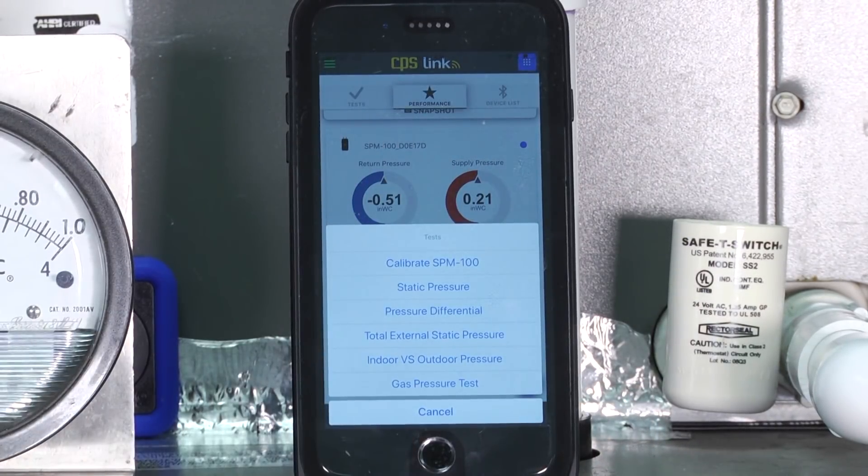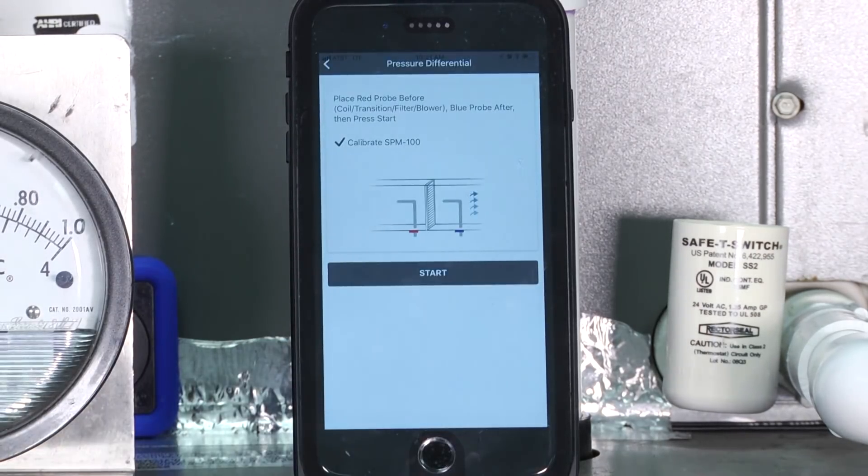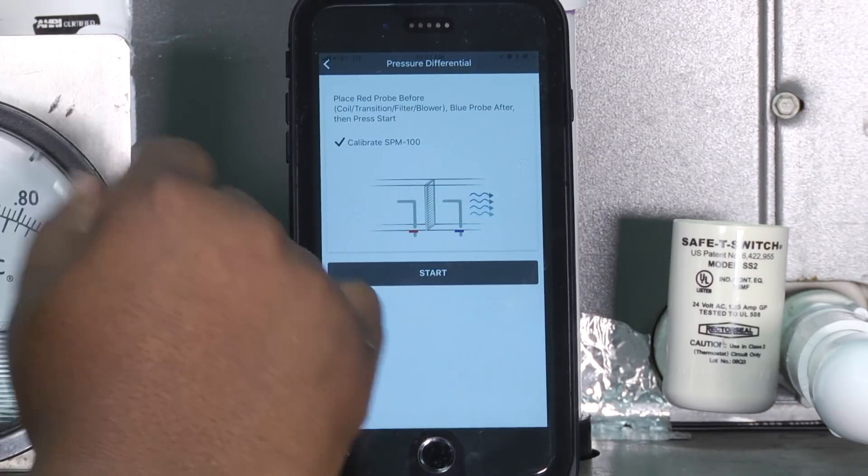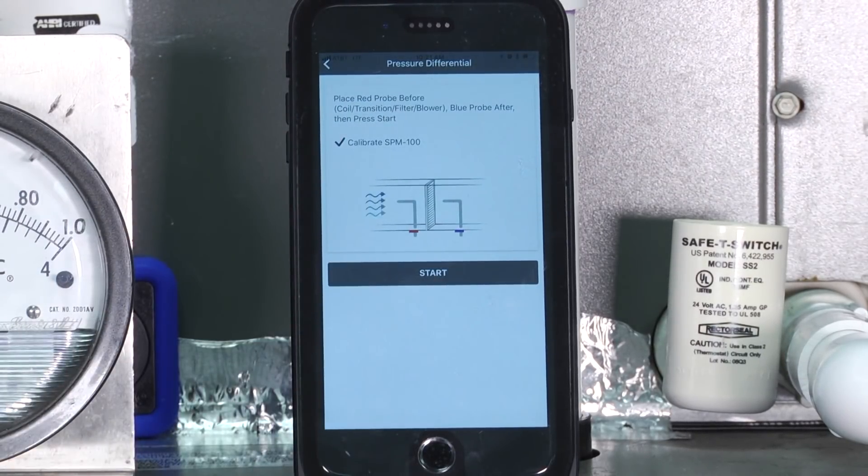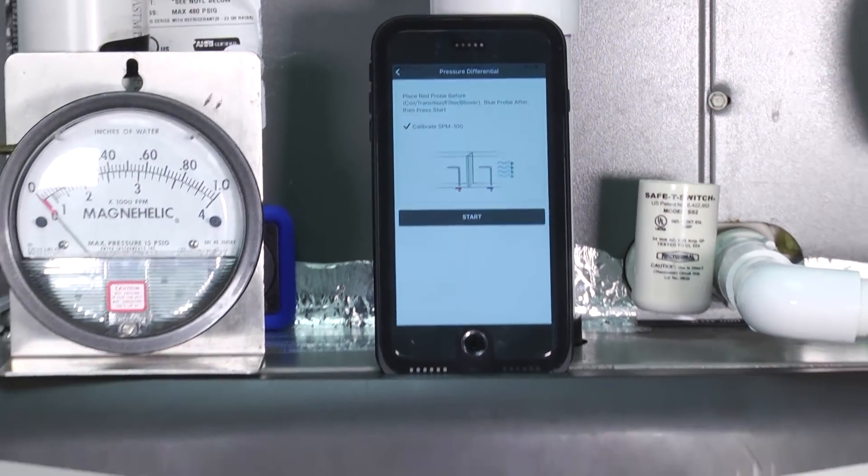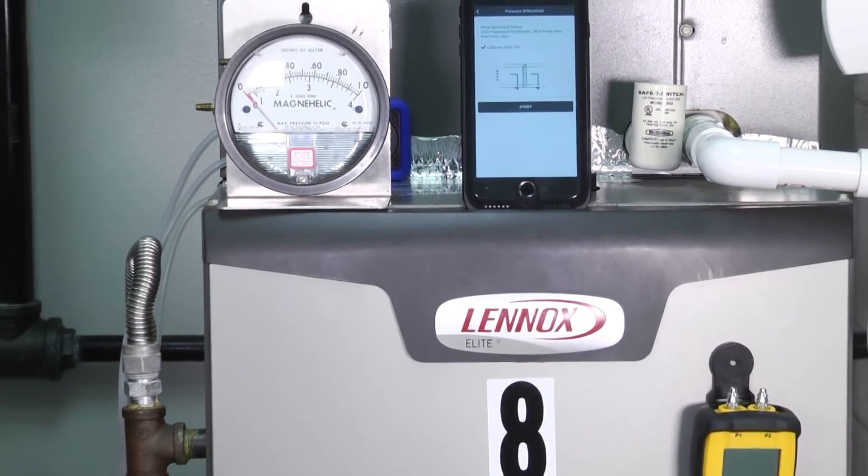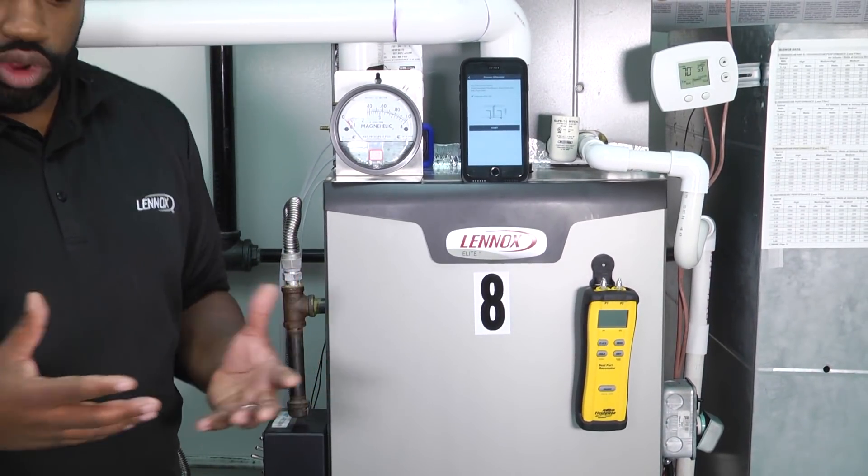I can go to pressure differential. If you see closely, I can check a drop over a coil, a transition, a filter, or just the blower depending on where I place my probes. Basically what you're going to do is sandwich the thing you're trying to get a pressure drop across. All of these tools can be used to help you calculate and dial in what your static pressure is.